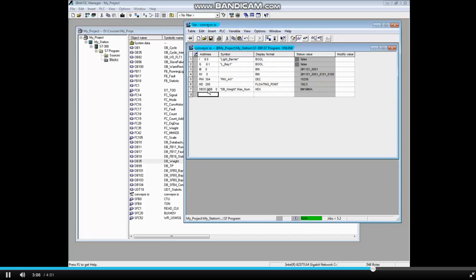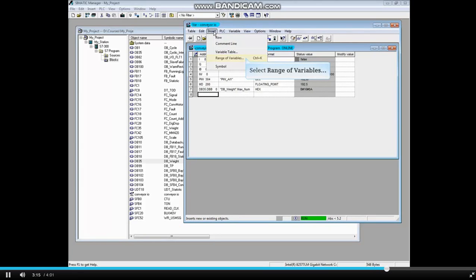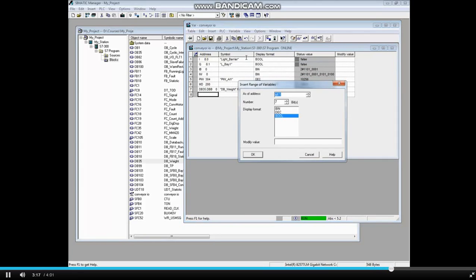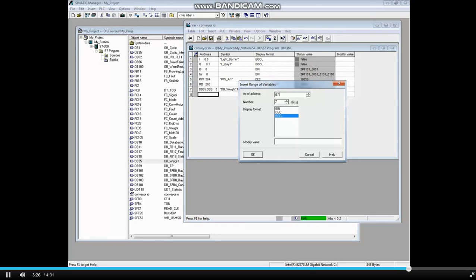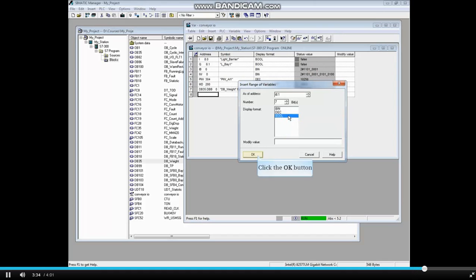A nice feature of the variable table is that you can insert a variable range to monitor. Click the insert menu and select range of variables. Type the beginning address, which can be bits, bytes, words or double words. Let's type input 8.1 and show the next 7 bits. We'll make the display format boolean, which displays true, false instead of 0, 1. And click OK.